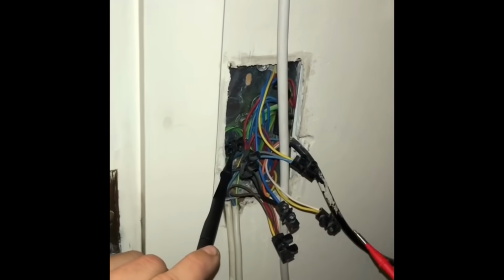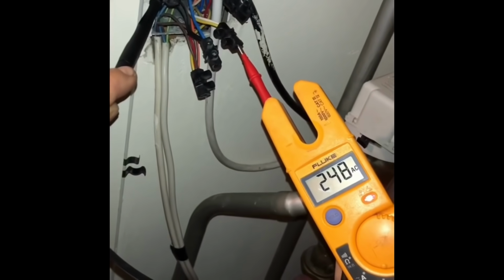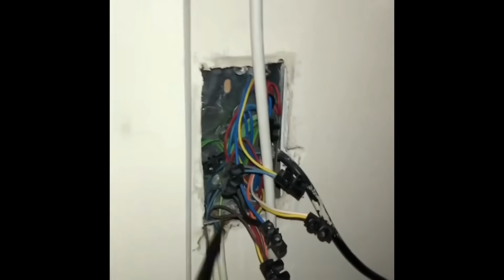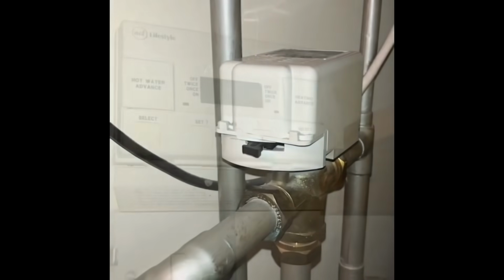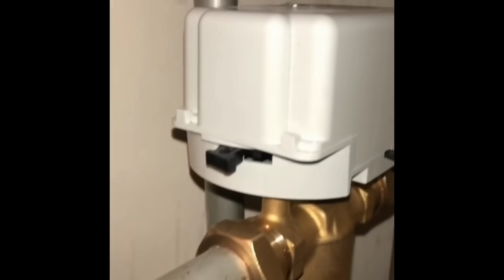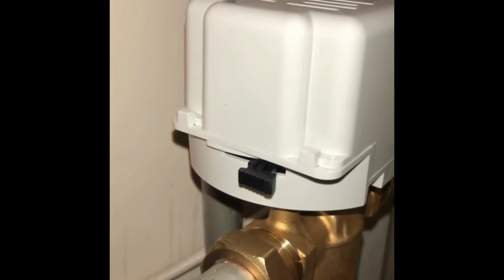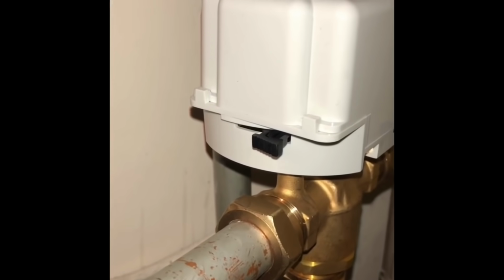Back up in the wiring centre on the yellow cable, we've got 240 volts. That confirms that the room stat is working. Putting 240 volts onto the motorised valve, but the valve's not opening. That proves that the fault lies with the motorised valve. Stick a new valve on, now it's all good.